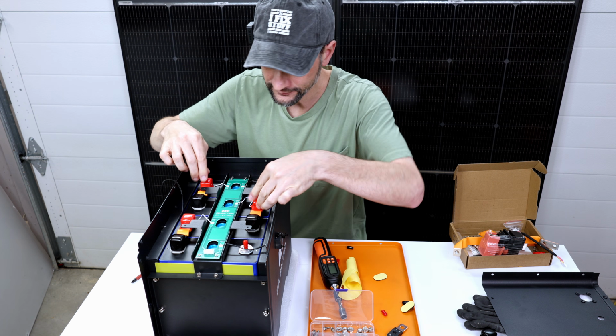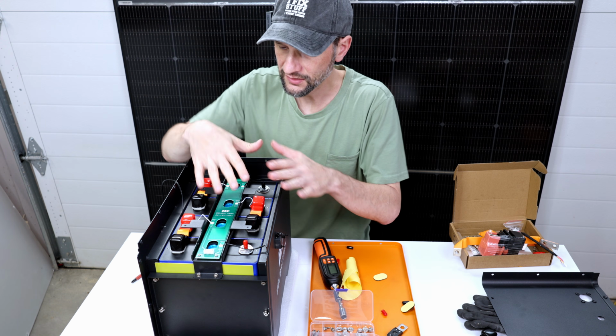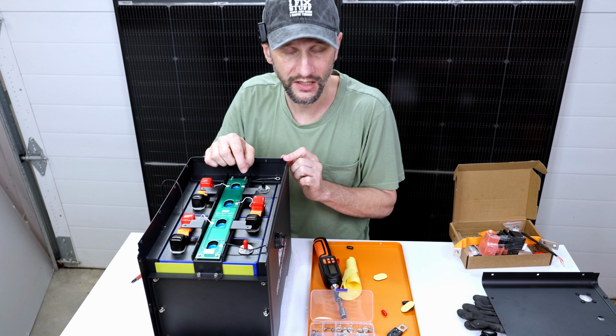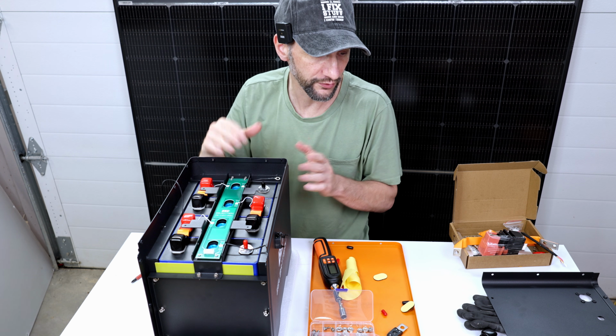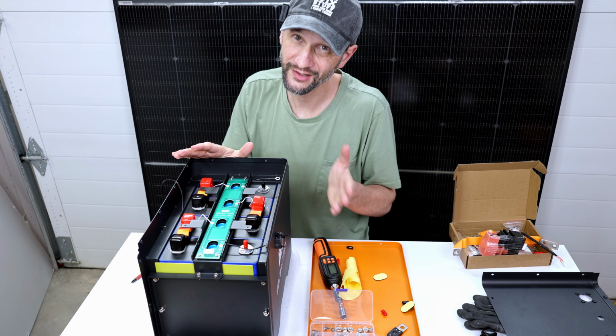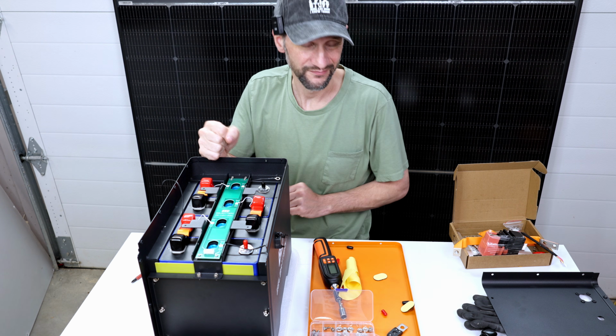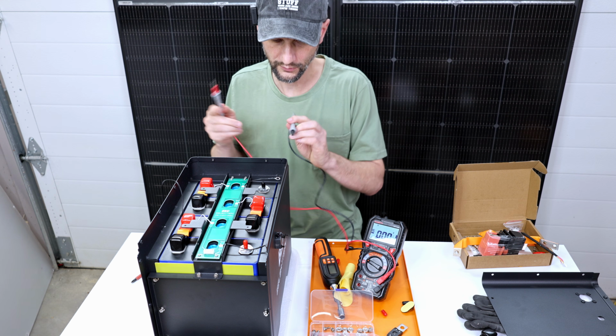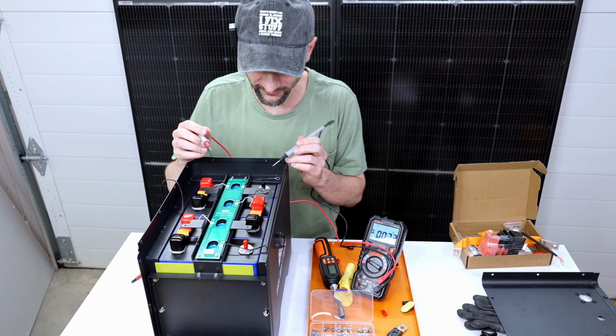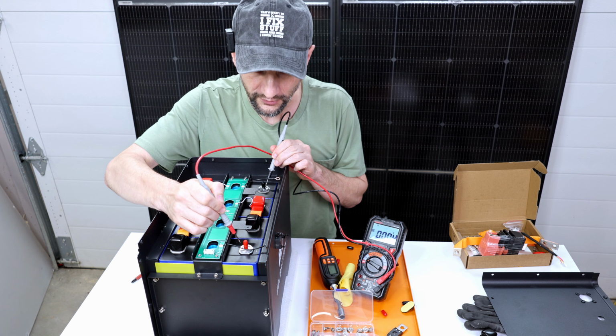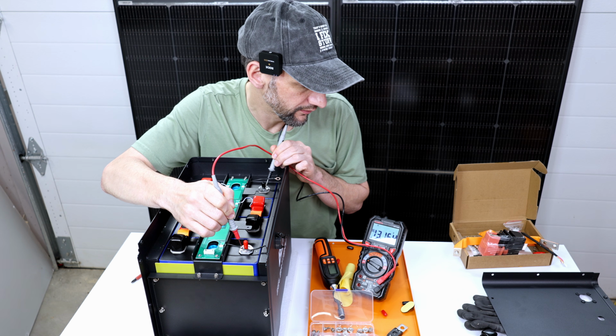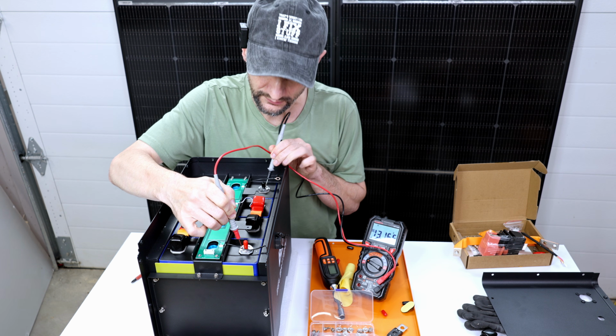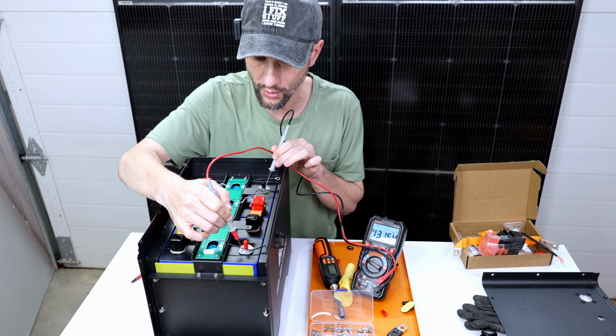But I got them on there, it's doable. Now, before I get the BMS and everything connected, I want to check the voltage across the terminals and make sure everything is connected right, because you don't want to do it backwards. I should have a little over 13 volts across the final terminals, and I'm reading 13.16, so everything is connected properly.